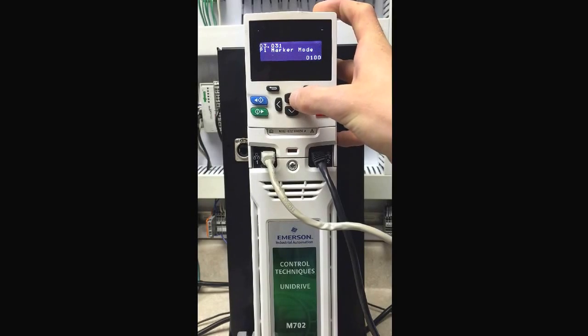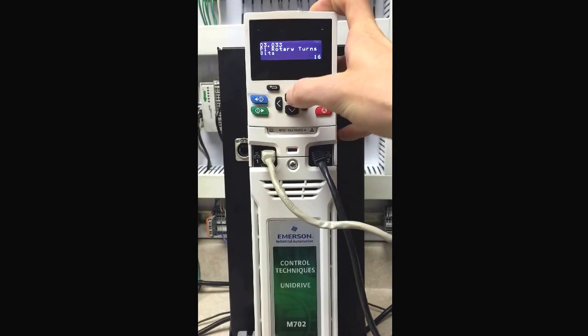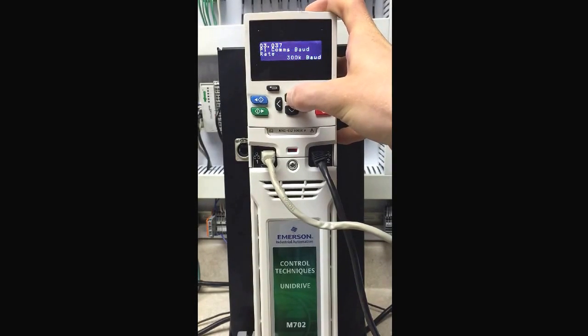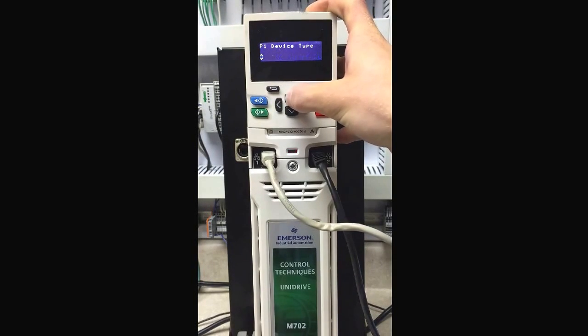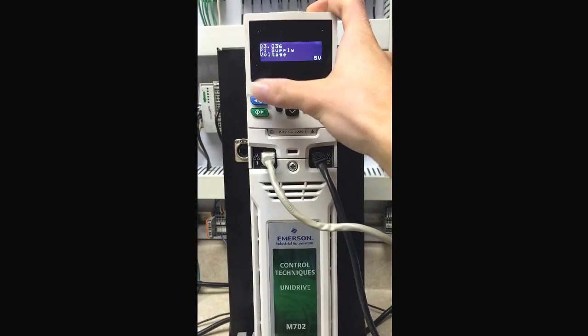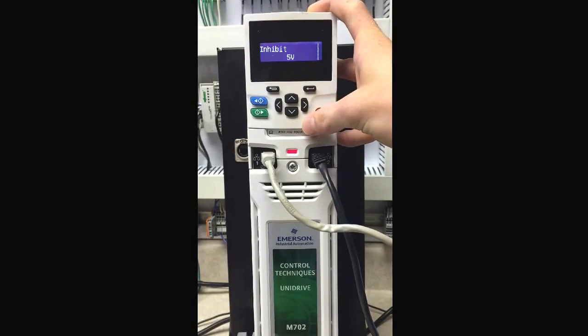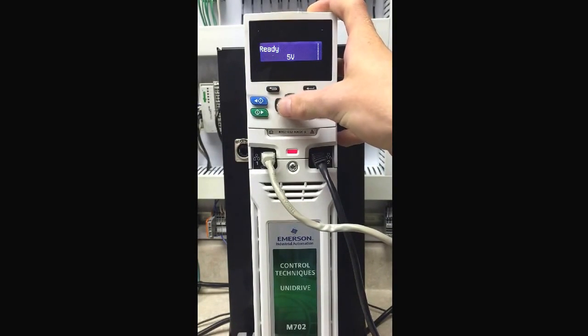We will now set up our encoder information. This is an EnDat encoder. Right now we have a trip, encoder trip. Set reset, now our trip is gone, we're inhibited.